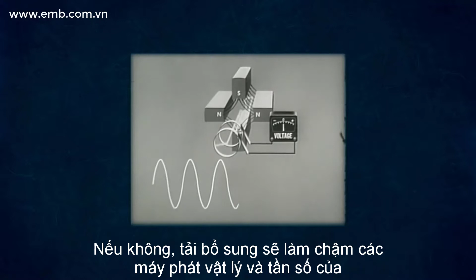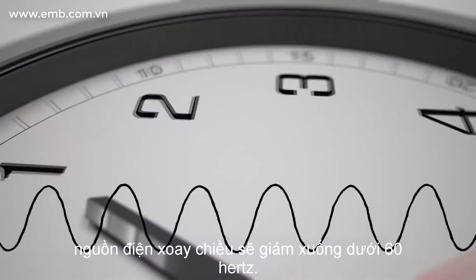When demand spikes, we need generators spun up to match it. Otherwise, the extra load will bog down the physical generators and the frequency of the AC power will fall below 60 Hz. The consequences of the AC frequency deviating by too much are massive because every generator in the entire system is magnetically coupled. If parts of the system lose synchronization, both generators and equipment connected to the grid can tear themselves apart. Because of that, most parts of the grid, including generation facilities, have breakers that trip to isolate equipment if the frequency deviates too far.